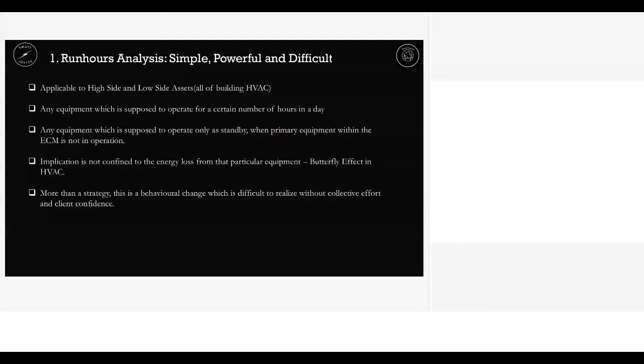So there is a butterfly effect in the HVAC system. If one air handling unit runs for more time, the chill water pump sitting in the plant room has to pump more water to cool the area or reach the water there. At the same time, the chiller will have more load because of this. So there are multiple repercussions for a machine not being shut down at a certain time - and this is where run hours analysis and data-oriented decision making comes in.